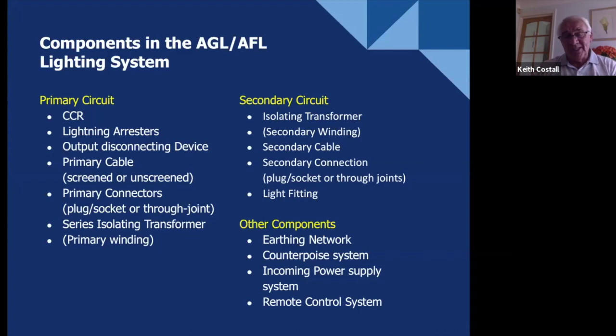There's also this thing called an output disconnecting device. It's offered by many suppliers, and it sits between the CCR and the field cable. So you can pull it out and push it back in, and it can be multifunctional where you can put an earth on the circuit if you want to do some fault diagnosis. So an output disconnecting device is something as well. The cable. Now the cable is screened or unscreened. What do I mean by screened? It means that there is a protective screen, which is a conductive piece of material. It gives mechanical protection, but it also helps with electrical protection.